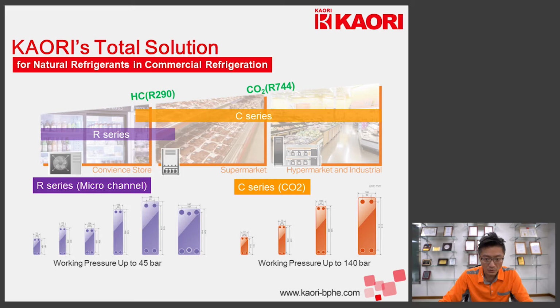And this is where the microchannel comes in. By using microchannel, we are able to reduce the amount of refrigerant charge and save the weight of the brazed plate heat exchanger. Another choice is the CO2 system, which only has global warming potential of 1. However, its high working pressure is hard for the system components. But here, Kaori offers brazed plate heat exchangers with maximum working pressure up to 140 bars. This makes the CO2 system easier to handle.